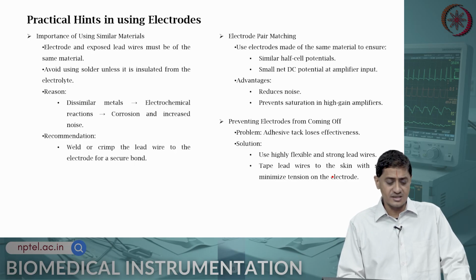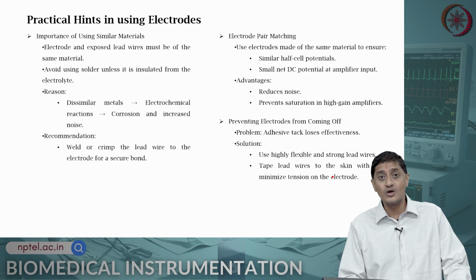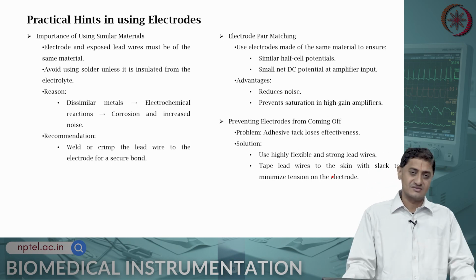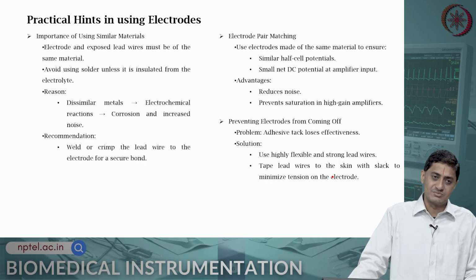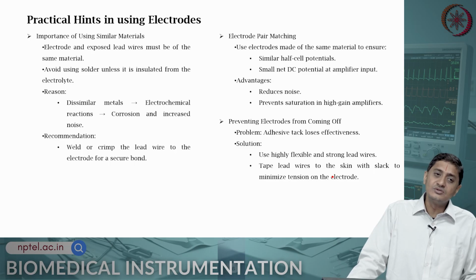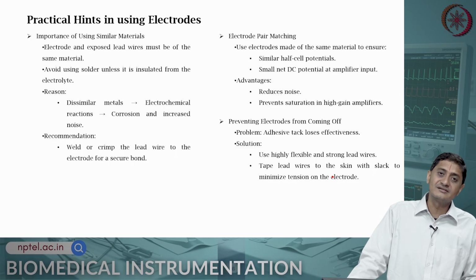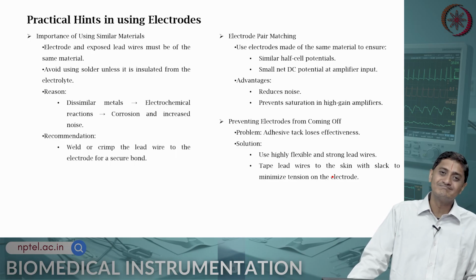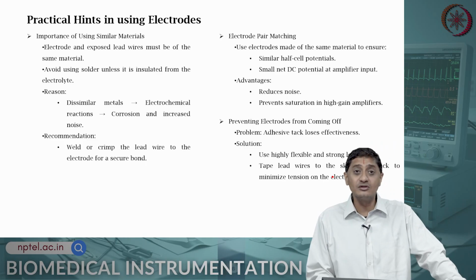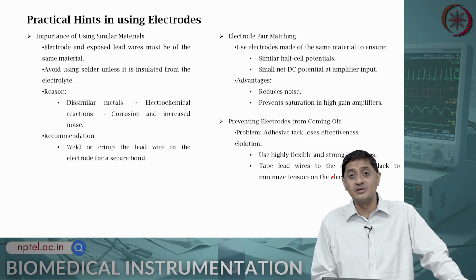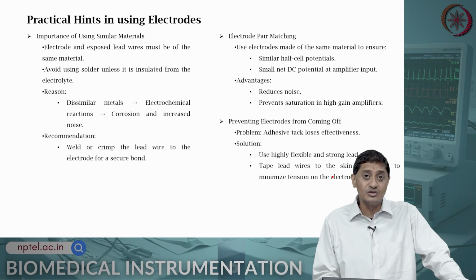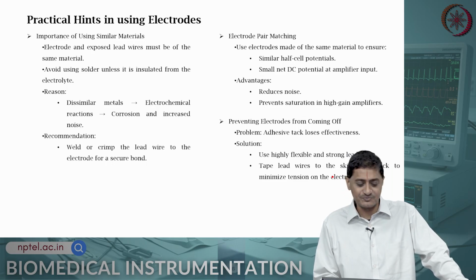Avoid using solder unless it is insulated from the electrolyte. It is absolutely important. So, do not use solder to connect two metals. Soldering is not permitted in this method. So, essentially in your fabrication we need to use welding or crimping of the lead wire to the electrode for a secure bond, rather than using solder to connect two points of the electrode. Although they are made of the same metal, solder should not be used in the middle because this will cause two dissimilar junctions, one with the first metal and the other with the second part of the same metal.